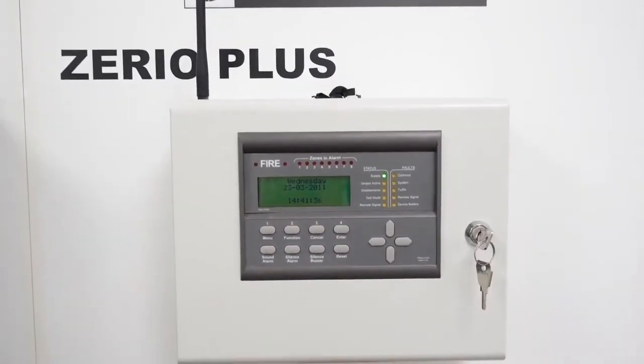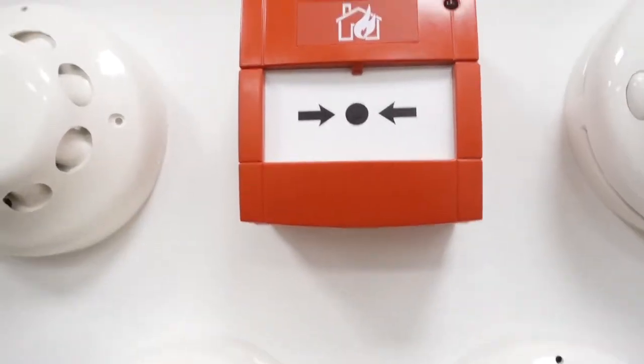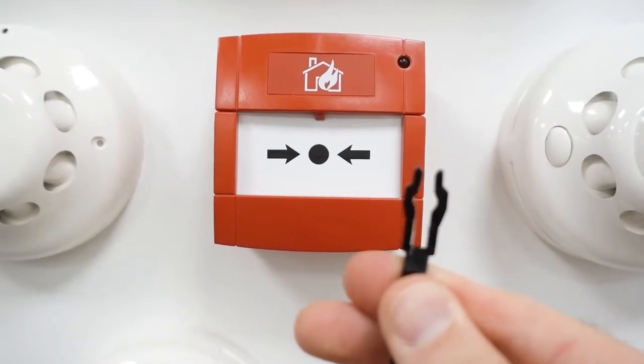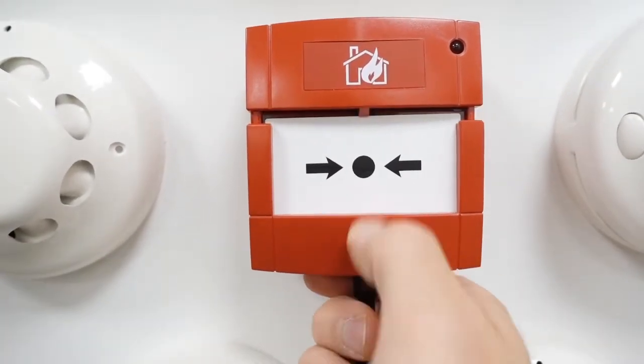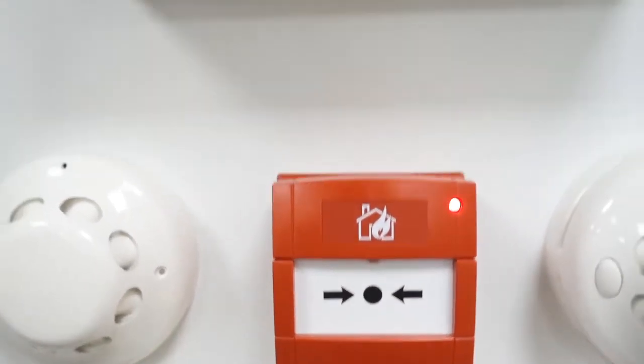This is the Electro Detector Zerio Plus — it's a radio system, it's a neat little system. And this is the call point. Again we're using the two-pronged test key, so we're going to put that up inside, pull it down with your thumb, wait for the red light, then put it back together.